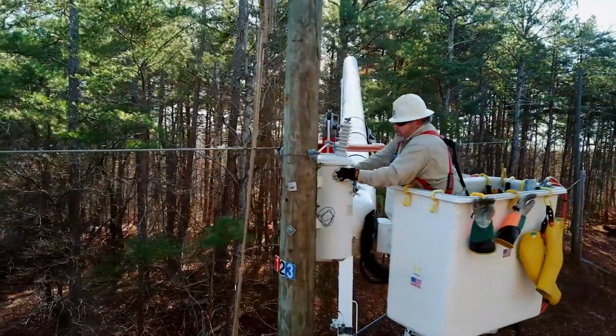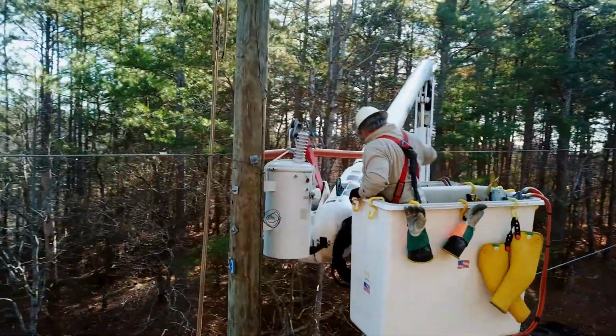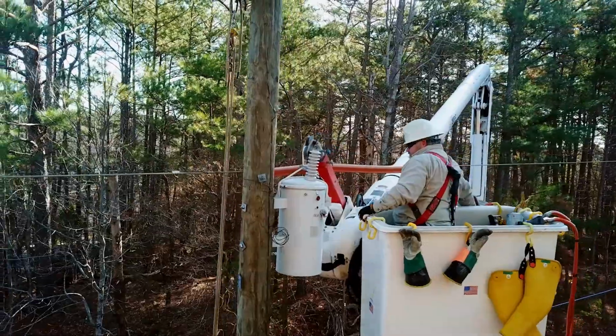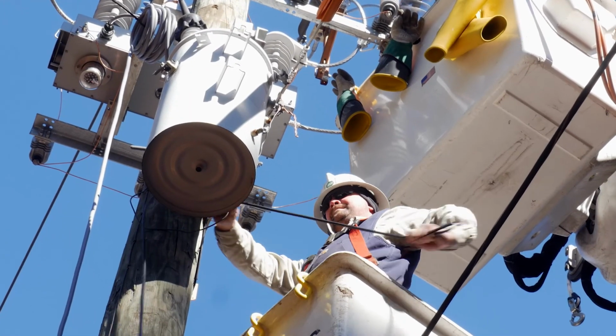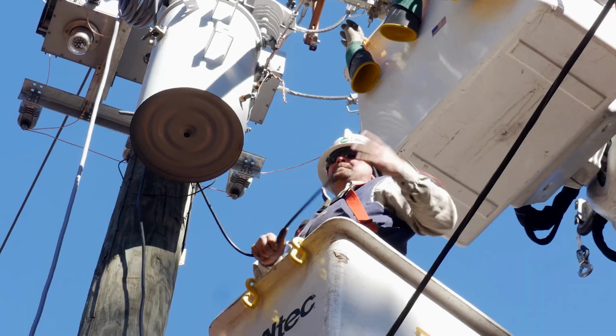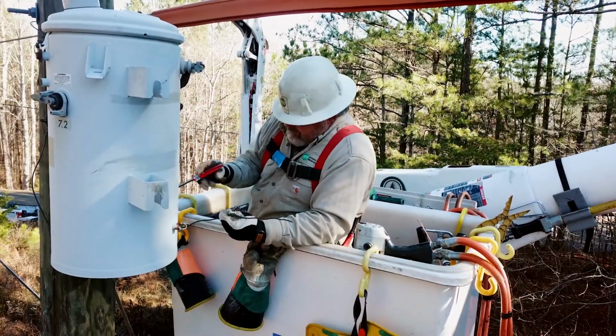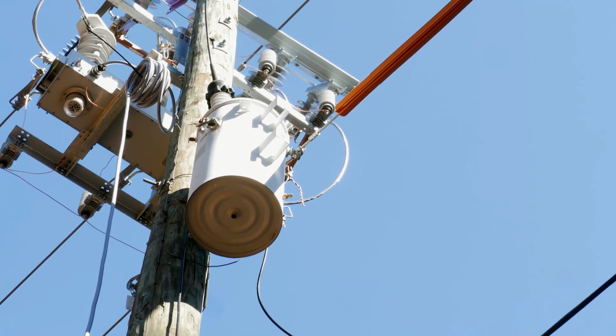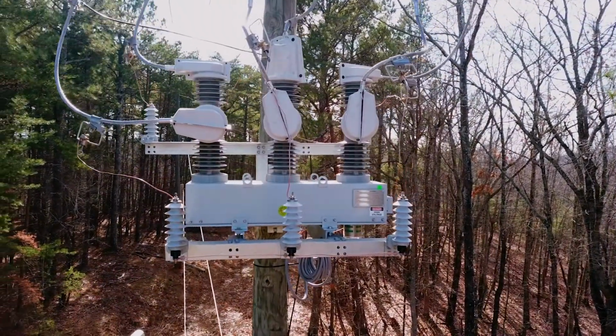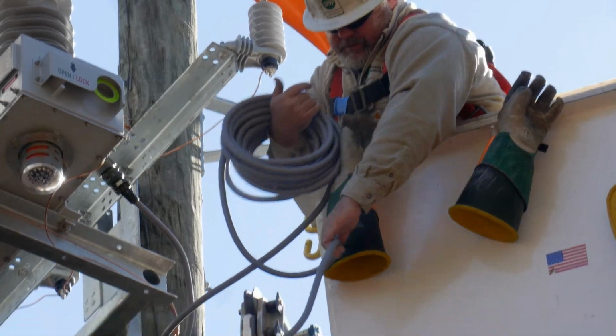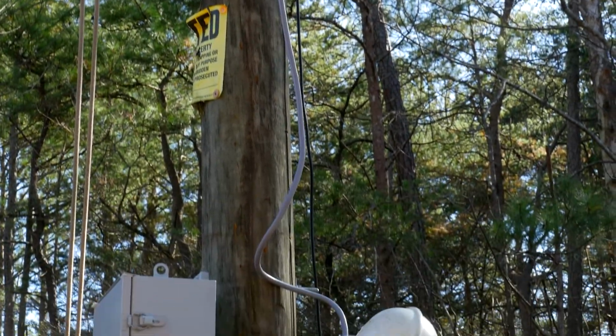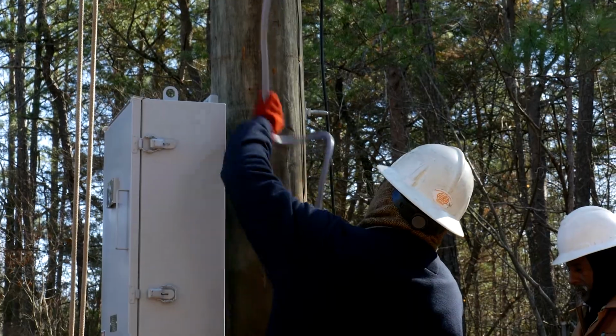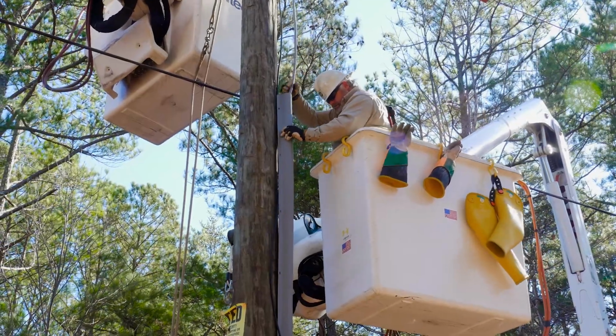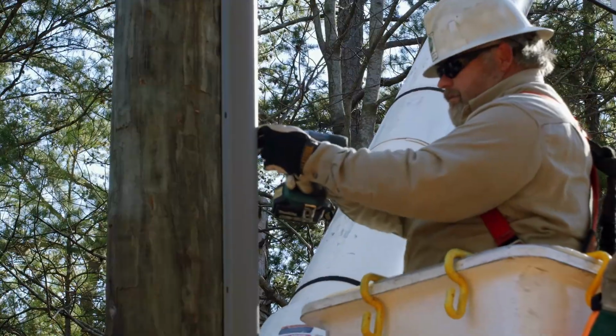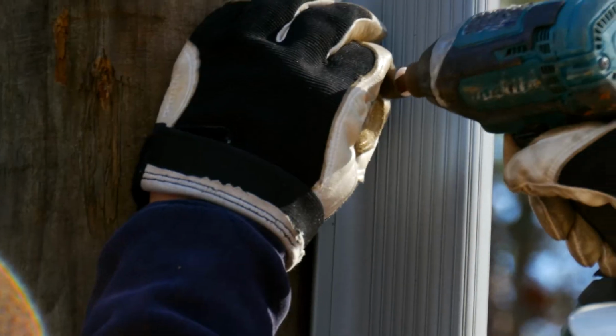Each recloser requires a provision for AC power in the control cabinet. To accomplish this, utilities typically supply a small transformer rated as low as 1.5 kVA on the back side of the pole. With the recloser and transformer installation completed on the pole, the utility can begin bringing the power and control cables, both covered with a piece of U-guard for protection, down to the cabinet.